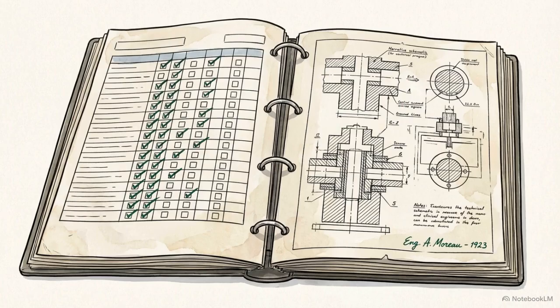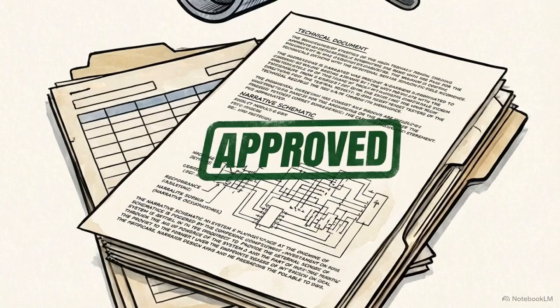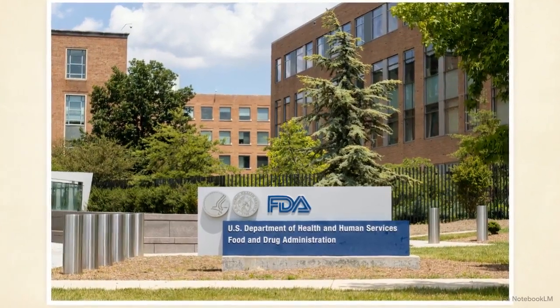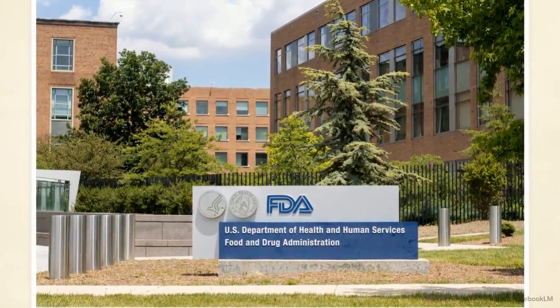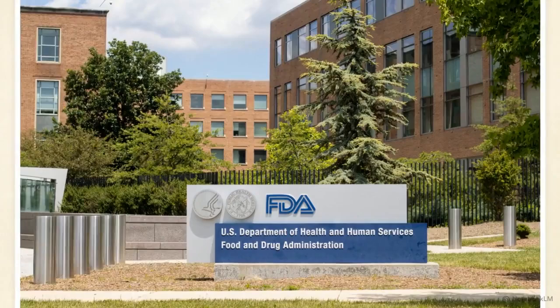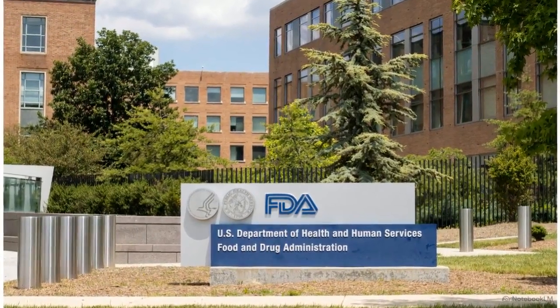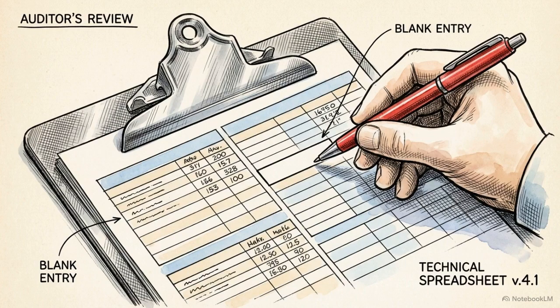The package must include sign-off sheets, laser elevation maps, and documented drain test results. This meticulous documentation is required by federal regulatory bodies to prove that the system is operating within safety standards. In a pharmaceutical environment, an undocumented slope is considered a failing slope by any regulatory auditor.